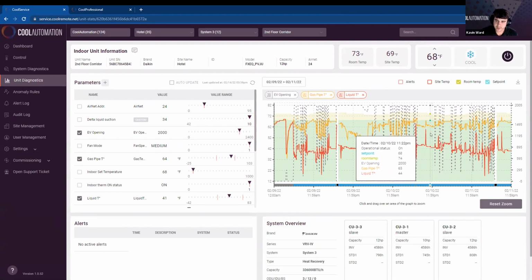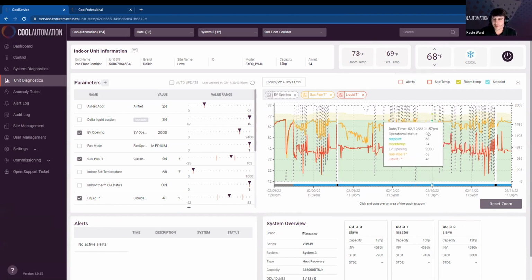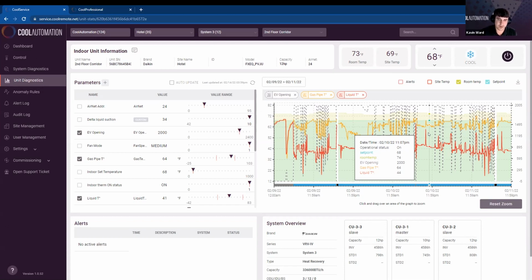So everything's operating. A VRF system is very robust and will try to continue to operate even as that refrigerant gets low. But ultimately, with the U0 error code, the system got to a critical point where it actually shut down and triggered that site to call for a support call, or to call their service provider in order to investigate the issue with the site.